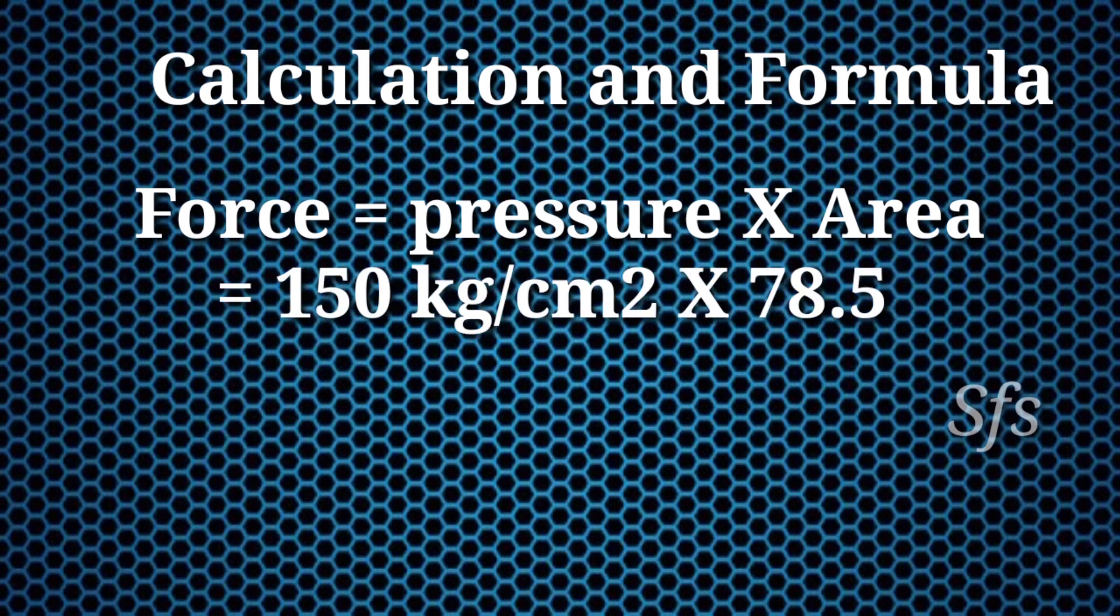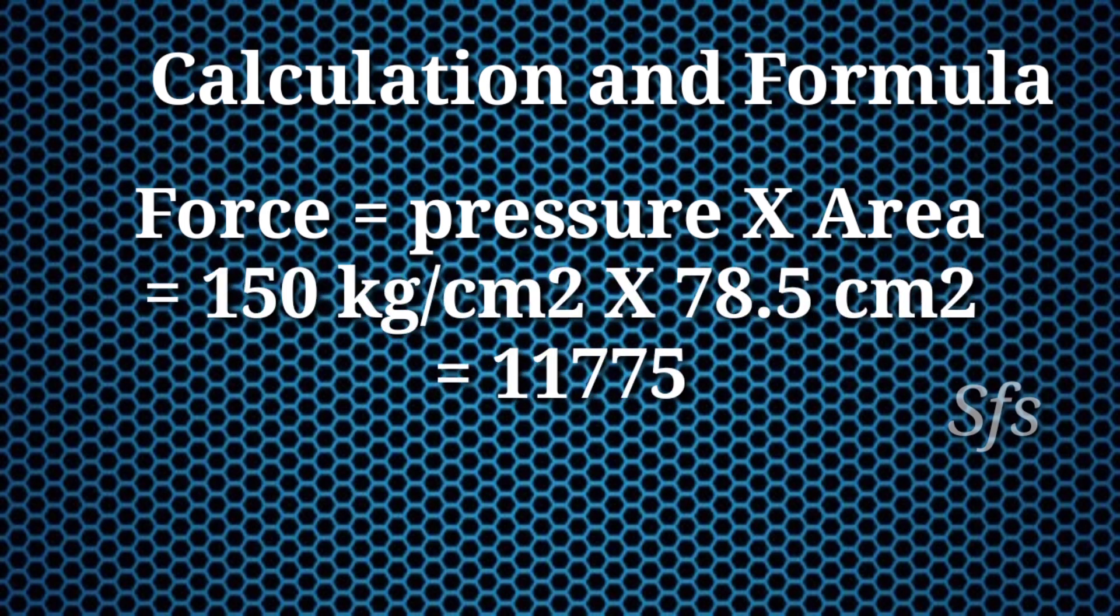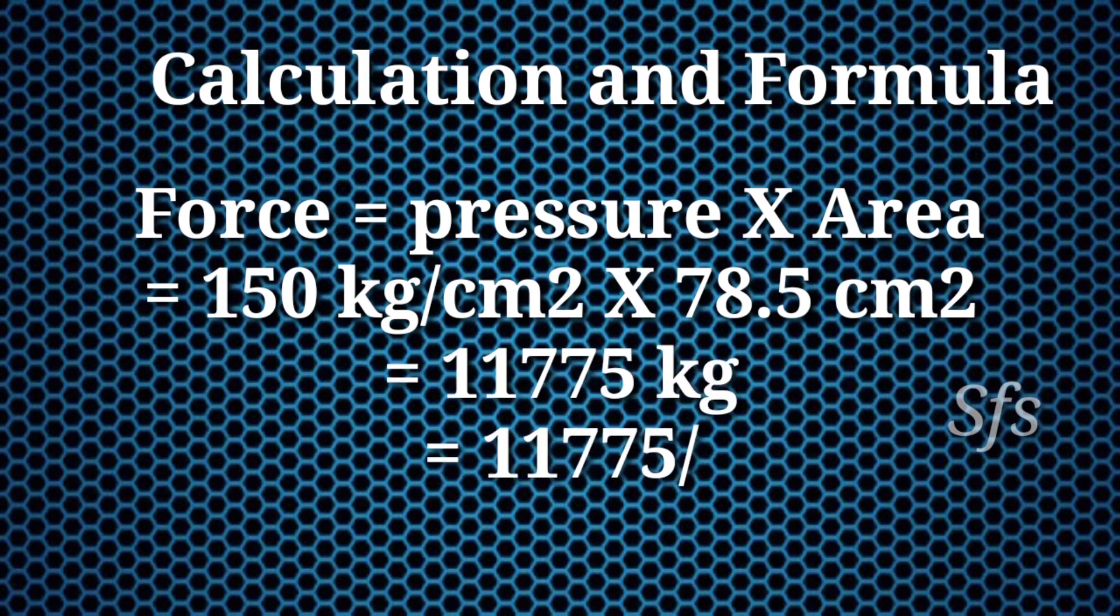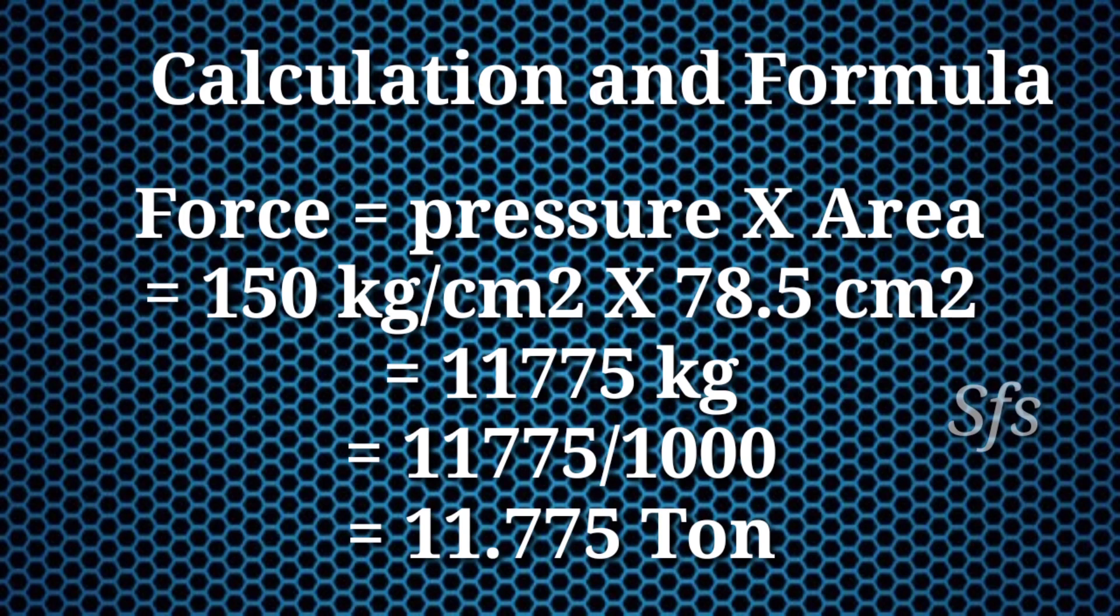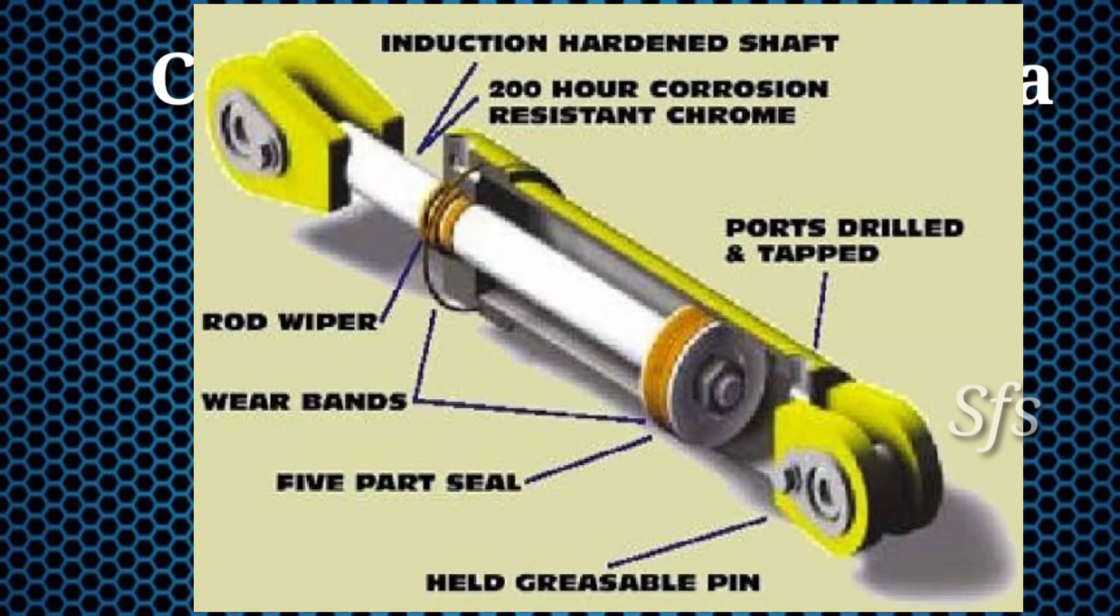Pressure is 150 kg per centimeter square and area is 78.5 centimeter square. By multiplying both, we get answer 11,775 kg. Converting to tons, we divide by 1000, getting 11.775 tons. This means a hydraulic cylinder with diameter 100 mm is capable to lift a load of 11.775 tons.